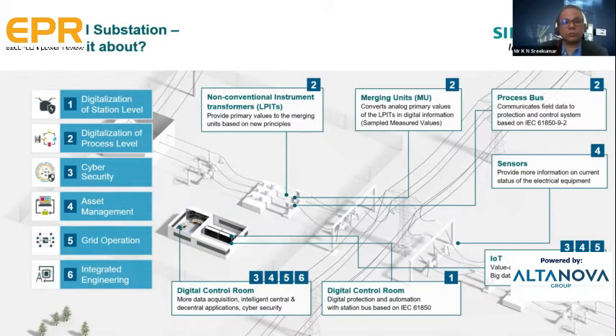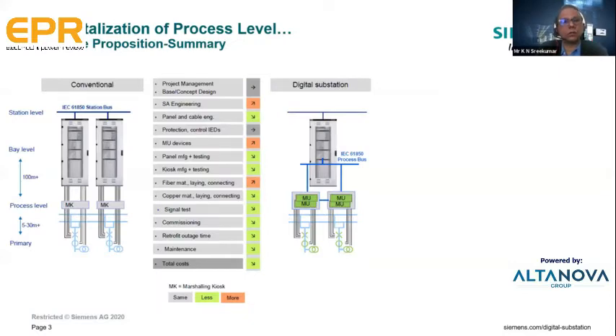And also integrated engineering, which means you now have the possibility to do the engineering of the entire substation using a process bus standard, and then do tests, configuration, and maintenance much more efficiently. It also fulfills the requirement of being much safer than conventional technology, where open circuit CTs could pose difficulties. So that's what a digital substation could do.